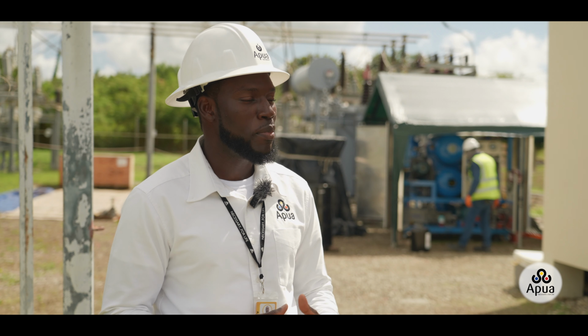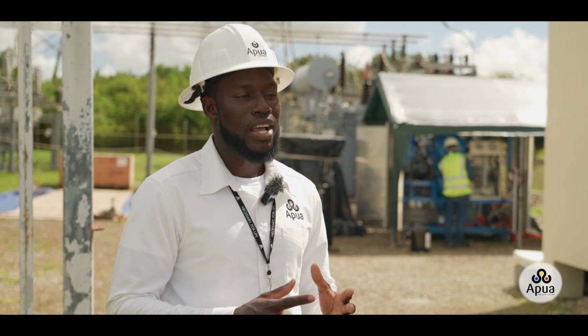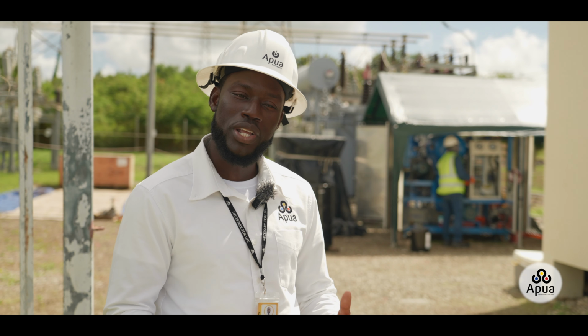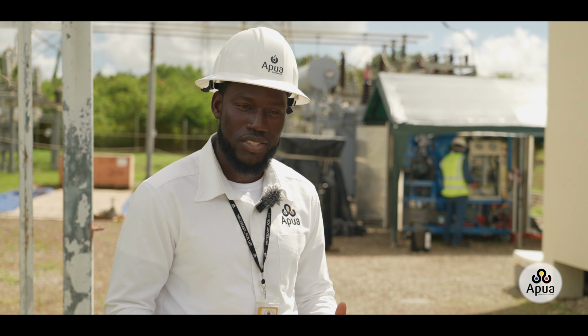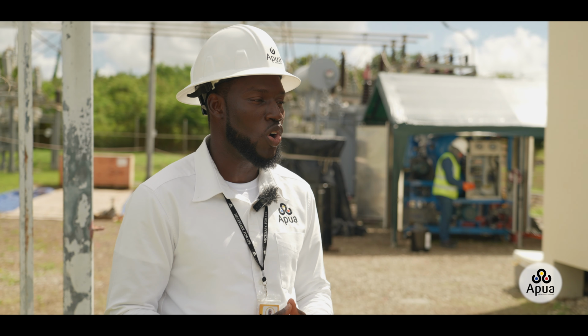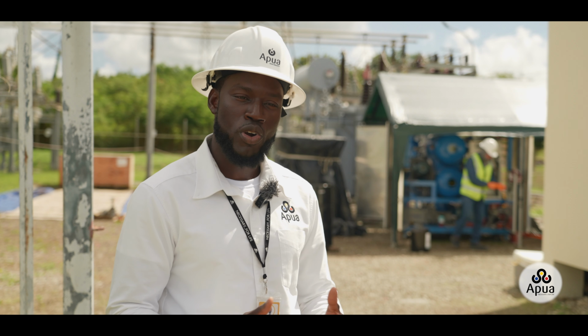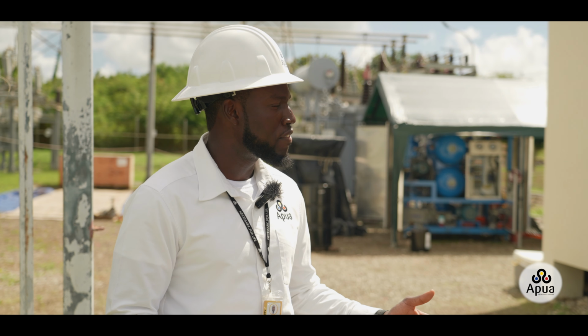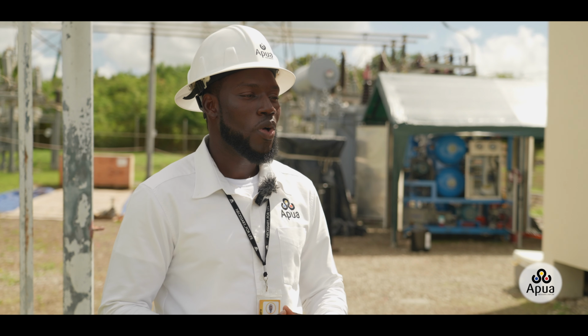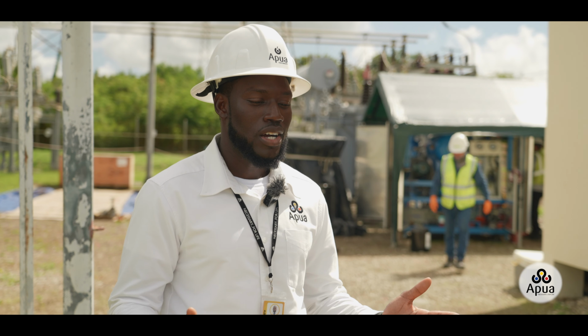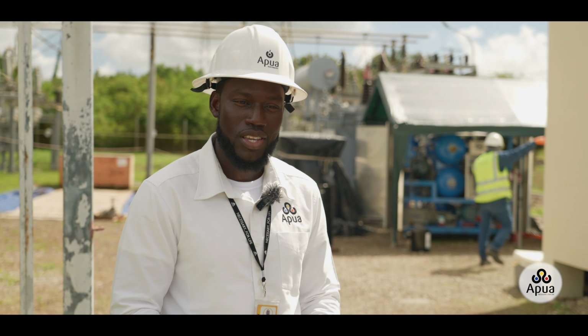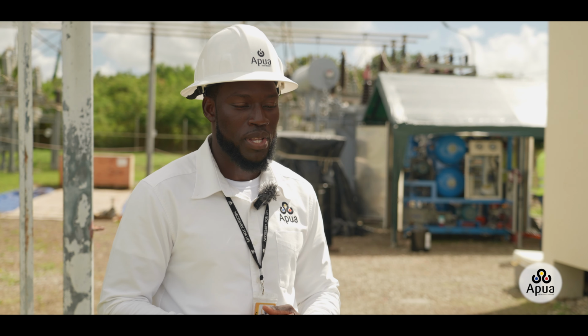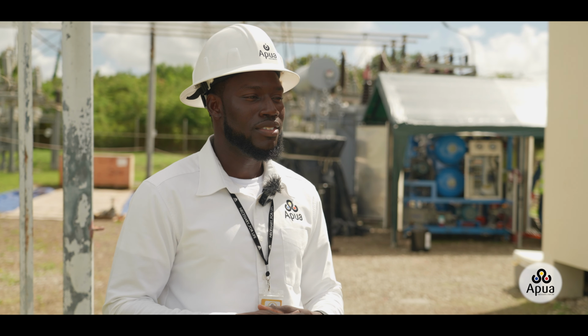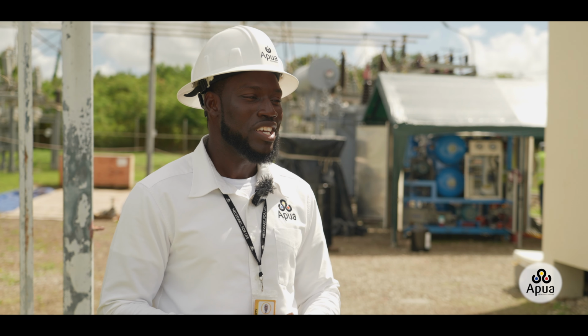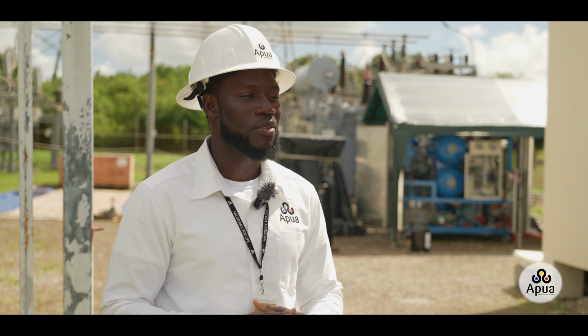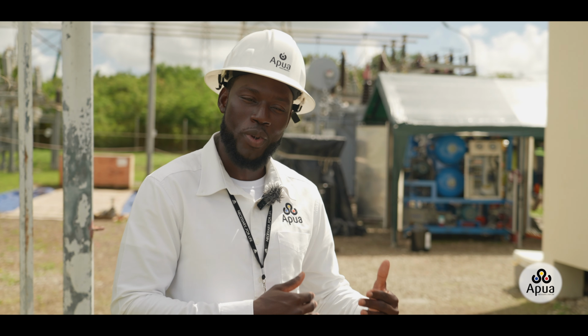So notwithstanding, yes, you may have a short period without power. That is, I guess, a better trade-off. Whereas if you do no maintenance, and then your transformer fails, you have a larger bill to face in terms of equipment failure. You could have probably damage to personnel. You could have damage to neighboring facilities within the substation. So now you have opened yourself up to a much deeper pit in terms of expense. Whereas if you plan preventive maintenance and perform it, yes, customers may be a bit uneasy about having that period of no power, but it's a better trade-off than having no maintenance and having a failure.